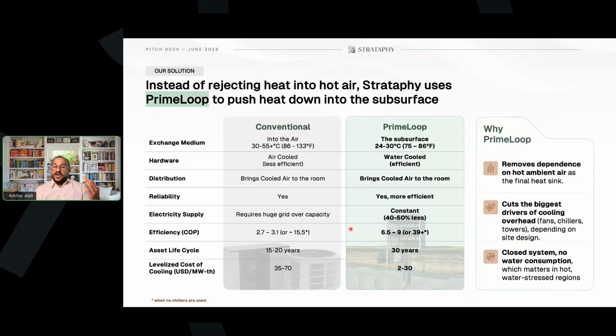Second thing, those systems are completely water-to-water exchange. So you're constantly using an exchange through water-to-water. You're not using any air medium. In all of the systems I talked about before, at a certain point you have a fluid exchanging heat with air. That's less efficient. The distribution could still be the same. This technology doesn't change anything about distribution. That's what liquid cooling does. And the reliability could also be the same. Typically, the reliability of geothermal systems is arguably higher, but let's say they're the same.